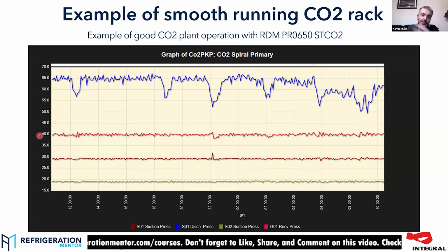So if they stop feeding product into this spiral freezer, the load will go through the floor because that product's coming in at like 80, 90 degrees C. And if you stop feeding or you stop the belt on the spiral, the load will drop through the floor immediately. So the system demands that you have quite a fast response time, but it's not subject to a lot of tiny fluctuations. The load is stable. If you've got 50 shop floor cases on it, you can't run the system with a fast reaction time because it will overreact to every little change in it. You've got to let things move around a little bit and let the system stabilize.